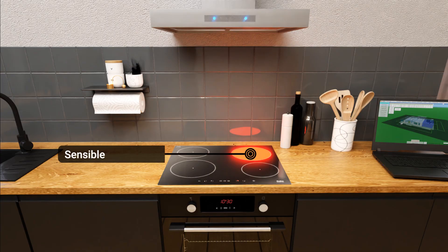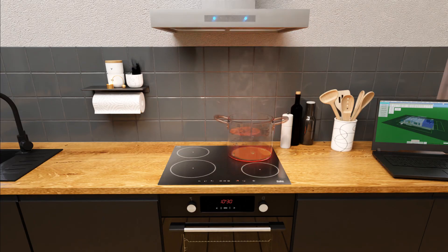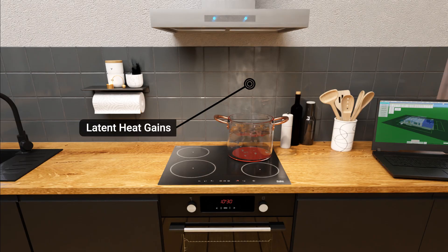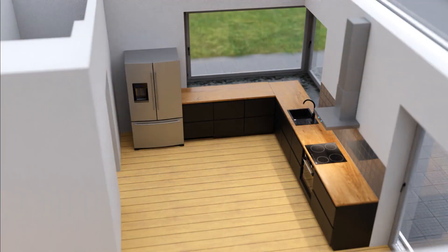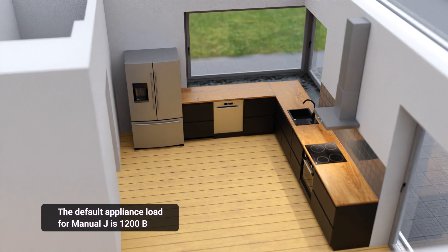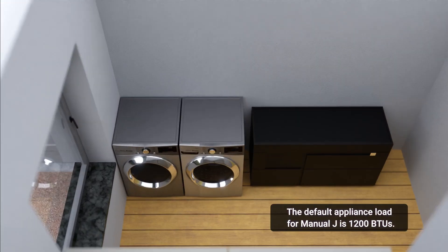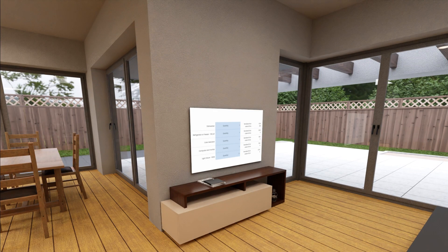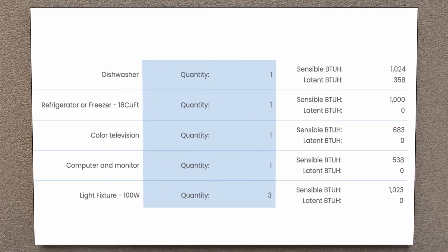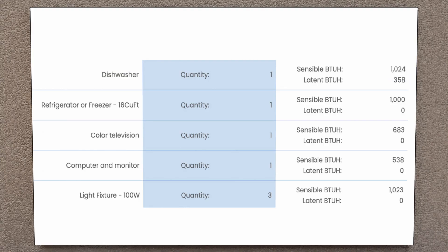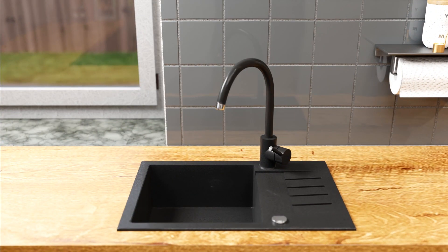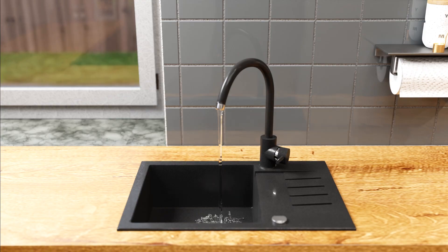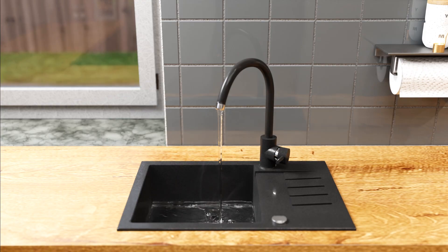Appliances also add heat. The default appliance load for Manual J is 1,200 BTUs. Electronics such as TVs and computers also give off heat when they run. Notice that the dishwasher adds latent BTUs, where the other appliances do not. In homes where occupants will wash a lot of dishes or clothes or take many showers, we can expect significant latent BTU gains.